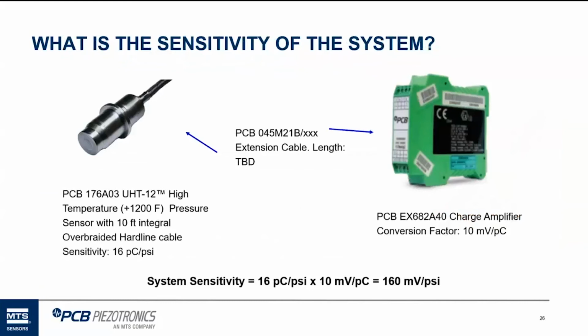So, a lot of times when I've talked about pressure sensors, people have asked, well, what is the sensitivity coming out of the sensor system? Is it voltage, or what is it if you're having a charge signal come out of the sensor? What is it going to be coming out of the charge amplifier? And what is a sensitivity? I went through this recently with a customer that bought a system that they wanted to configure their CDMS system side. They had a 176 style probe, which are high temperature probes, 176X something, depending on the probe. And the one they had was the 176A03. Its sensitivity is 16 picocoulombs per PSI.